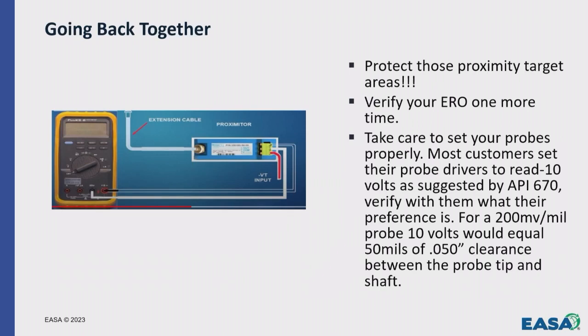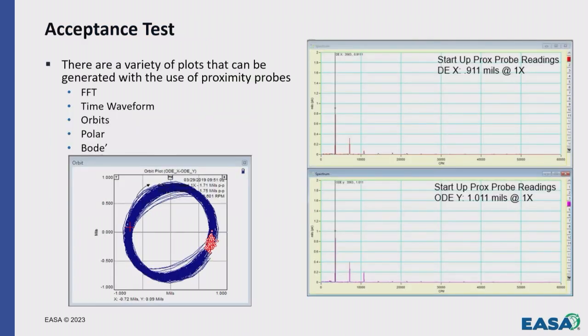Then going back together, we want to protect those Prox Probe areas very well. Verify your electrical runout one more time, and take care to set your probes properly. Most customers set them around 10 volts, which gives you about a 50 thousandths clearance. Don't try to use feeler gauges. That's not the most accurate way to set your proximity probe. You want to set them with a digital voltmeter. And you've got some different thicknesses of the tips, so 50 thousandths is usually the clearance you'll wind up with.